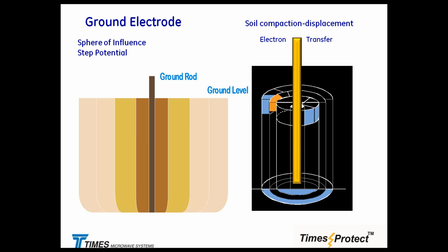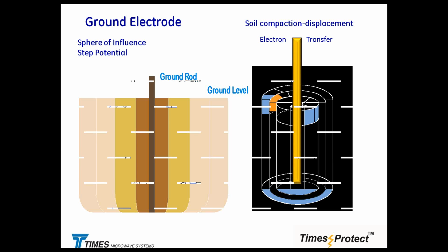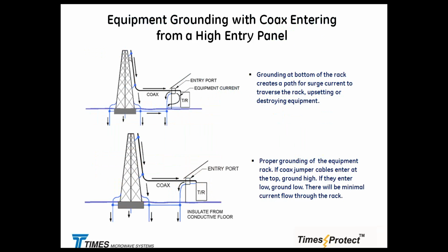If you're going to have a fairly acid soil, then the copper is going to get eaten pretty quickly down there. So if you use that bentonite to enhance it in challenging sites when it comes to grounding, this thing is going to last forever. Okay, so as you see, we started coming down from the top of the tower. We finished grounding jumpers. In this example, one is right below the antenna. Another one is going to be when we transition the RF feeder from the vertical to the horizontal. There is the cable tray.